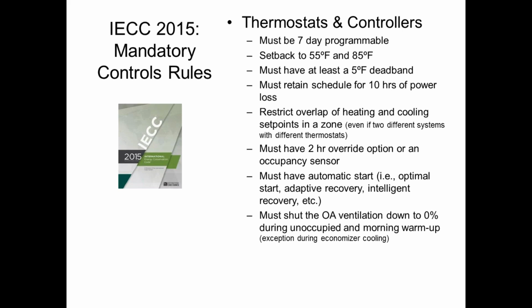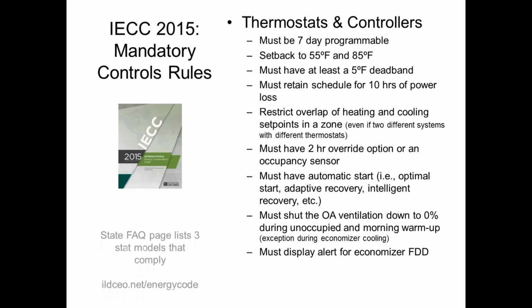You've got to shut the outside air damper like I mentioned. It doesn't say the stat has to do that, but something has to tell the economizer that it's unoccupied time and time to close its damper. I don't know what else that something would be. If it's not a BAS, because you don't have one, then it's going to have to be the thermostat, because there's nobody else involved that has the schedule. I guess your lighting schedule panel might know the schedule of the building and it could tell you, but that would be weird. All right, so you've got to have the damper shut off based on that. You've got to find a thermostat that has that. And then you've got to have a thermostat that has the ability to display these fault detection alarms as well.